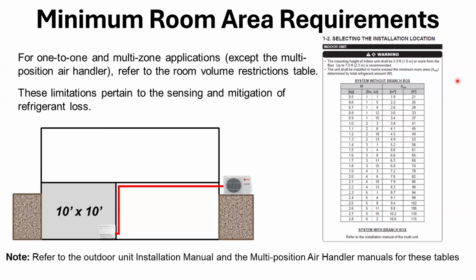Because it's either going to be a worksheet on a piece of paper, or you're going to use the DSB on each one of these jobs. And then you know ahead of time what your requirements are. So let's look at this. The mounting height of indoor units shall be 5.9 feet or more from the floor, and up to 7.5 feet is recommended. We're usually putting wall mount type units closer to the ceiling anyway, right? But this is looking at a floor unit, which is what they're showing right here.